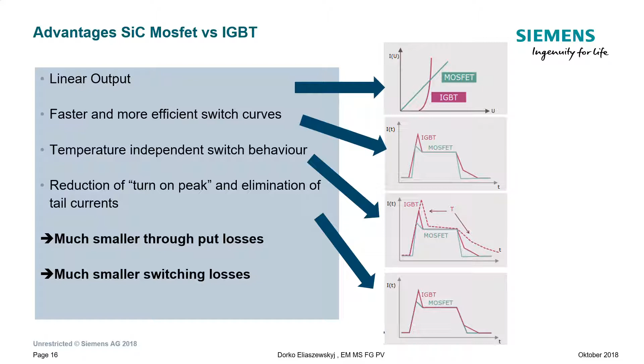It will change dramatically the electrical balance of plant world. It means it will also give an extra drive to the string inverters, because the string inverters will become smaller and cheaper. Just to give you this relation: the higher the efficiency, the less dissipation power you have, loss. That means you don't have such a strong demand for cooling. You can become smaller with your inverter, and if you're getting smaller, then you're getting cheaper. That is the relation we have to regard. So silicon carbide will make the inverters more attractive, especially the string inverters.